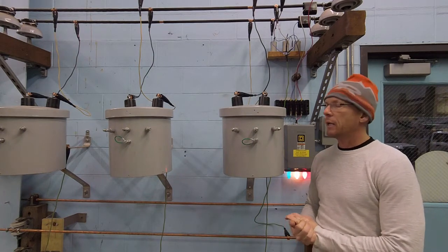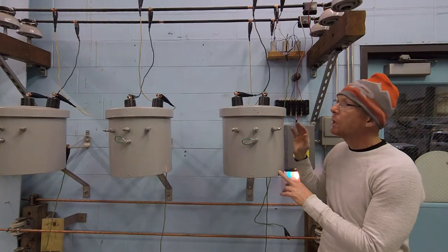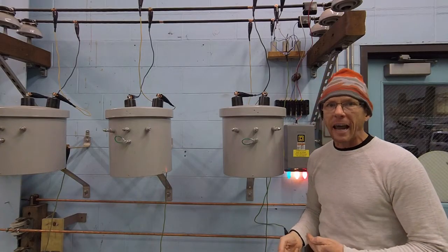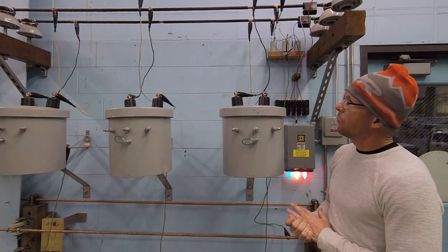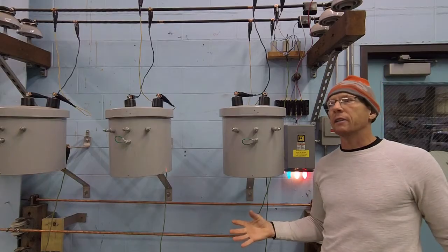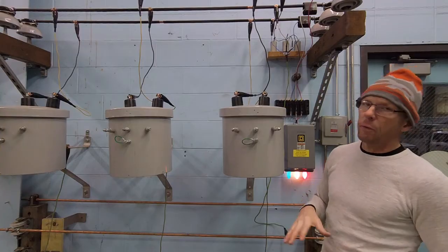If you're talking about an underground circuit being fed by, let's say, three conductors of one aught, five thousand feet long, you may only be looking at a couple hundred nanofarads of capacitance. And in this case, because our voltages up top are much lower, they're 120/208Y, we need a higher value of capacitance to kick this effect into action. There's a lot going on when you try to recreate this phenomenon, and it really expands beyond the ability of a simple video to explain, but I'm going to try to get through the basics of it.